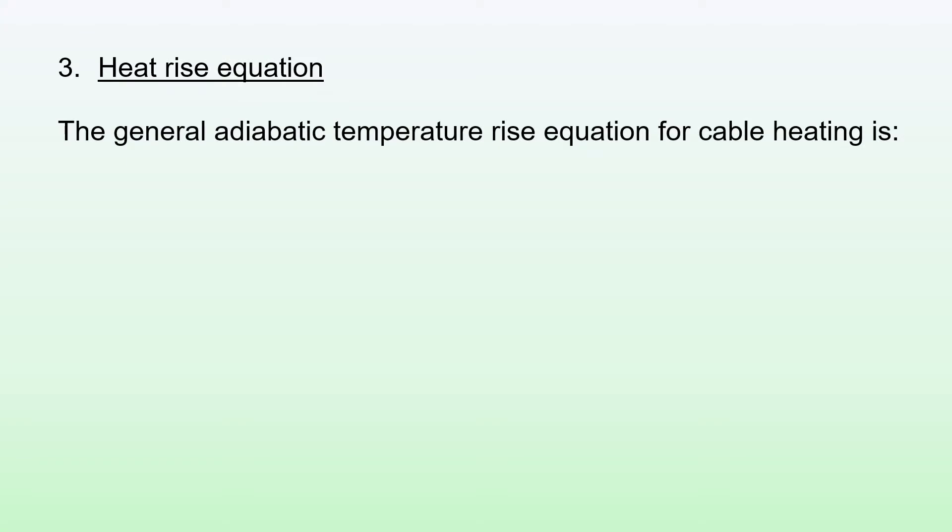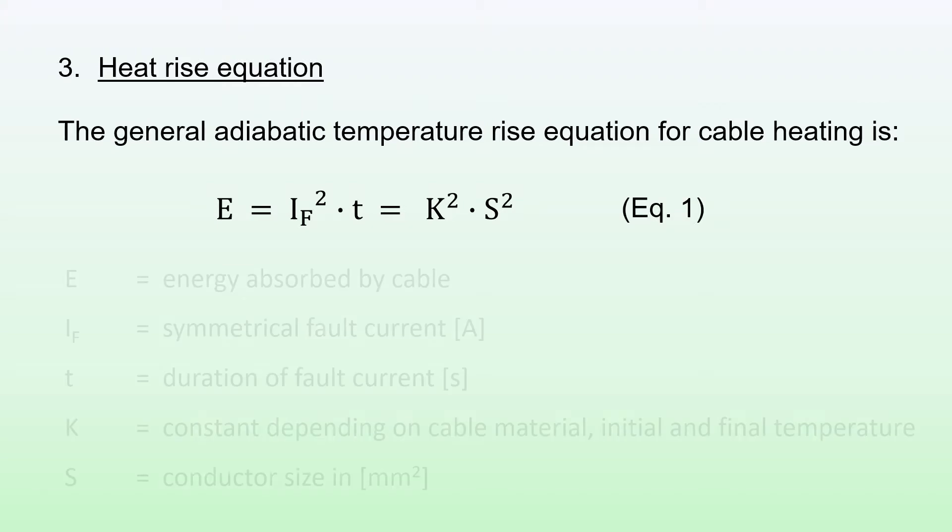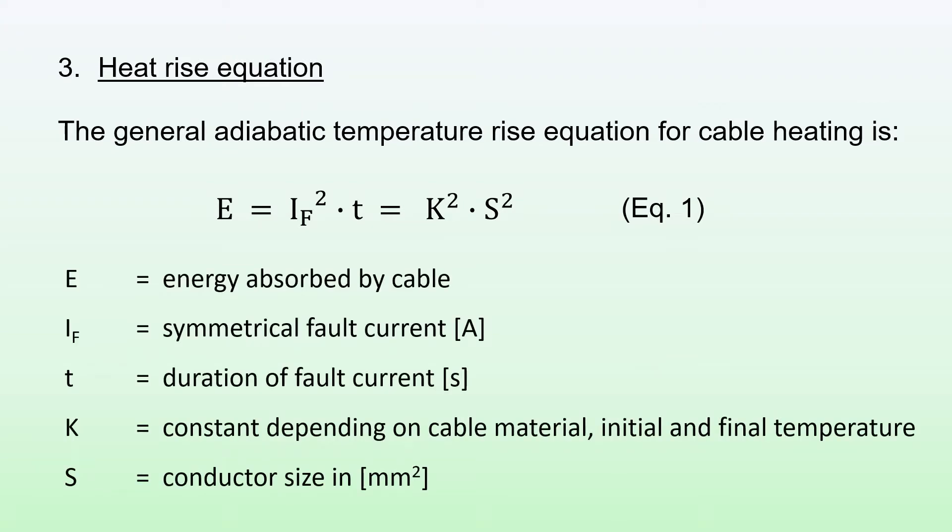Now looking at the heat rise equation, the general adiabatic temperature rise equation for cable heating is E equals If squared times t, which equals K squared times S squared. That's equation 1. E is the energy absorbed by cable, If is the symmetrical fault current in amps, t is the duration of the fault current in seconds, K is the constant depending on cable material, initial and final temperature, and S is the conductor size in millimeters squared.